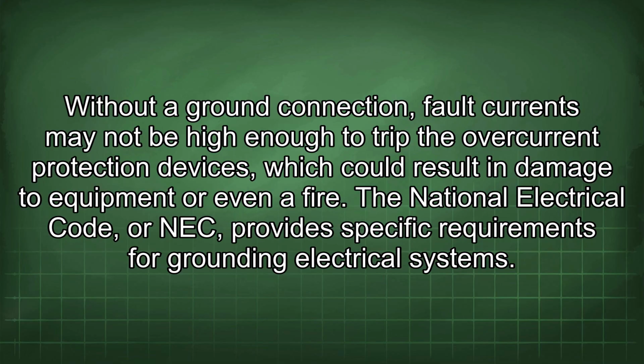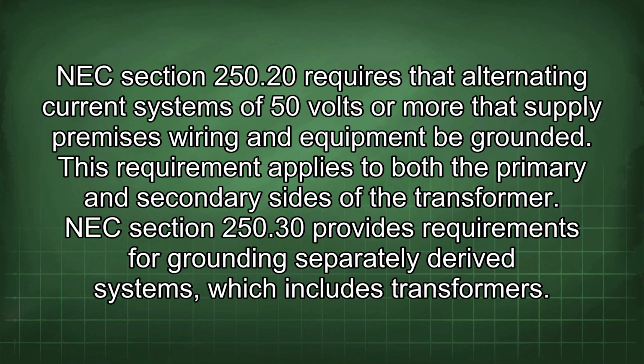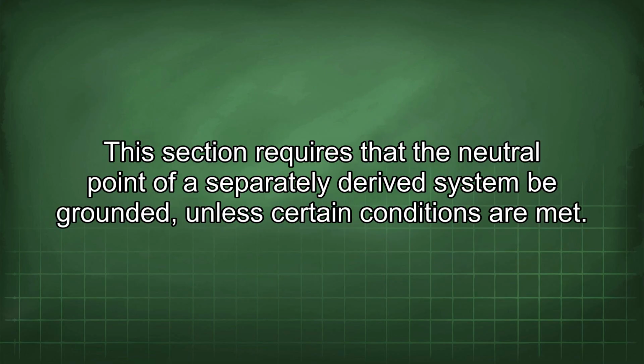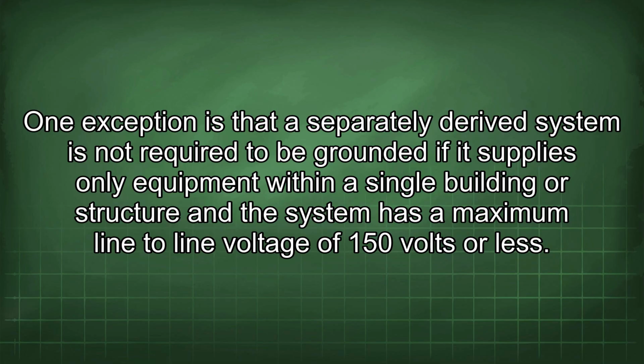The National Electrical Code, or NEC, provides specific requirements for grounding electrical systems. NEC Section 250.20 requires that alternating current systems of 50 volts or more that supply premises wiring and equipment be grounded. This requirement applies to both the primary and secondary sides of the transformer. NEC Section 250.30 provides requirements for grounding separately derived systems, which includes transformers. This section requires that the neutral point of a separately derived system be grounded, unless certain conditions are met. One exception is that a separately derived system is not required to be grounded if it supplies only equipment within a single building or structure and the system has a maximum line-to-line voltage of 150 volts or less.